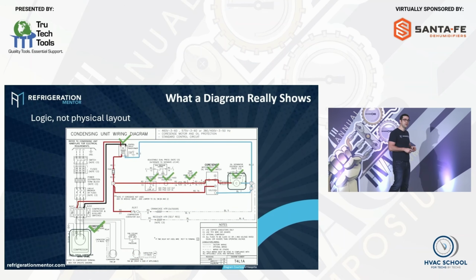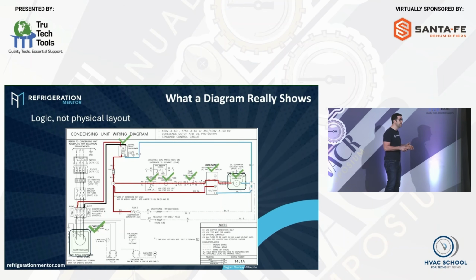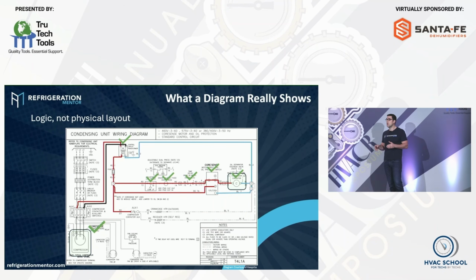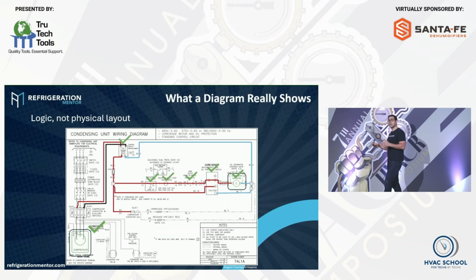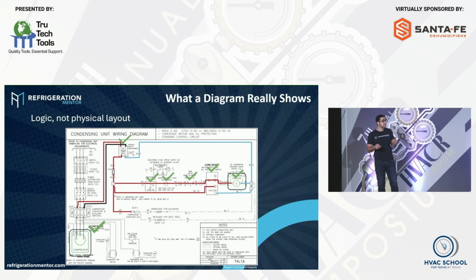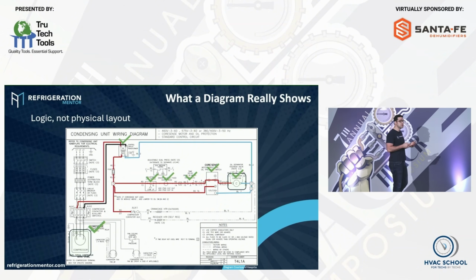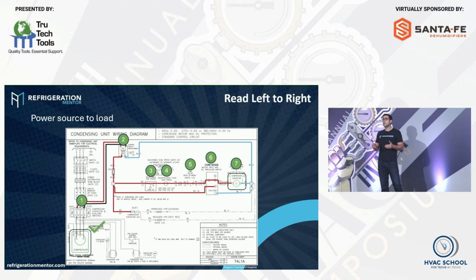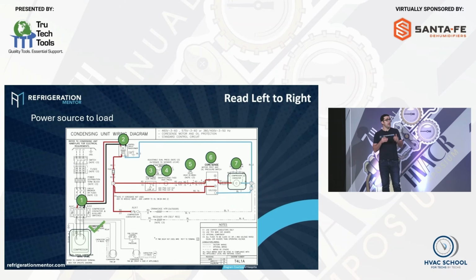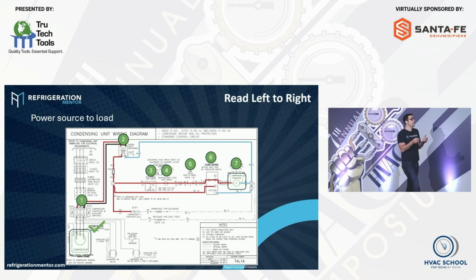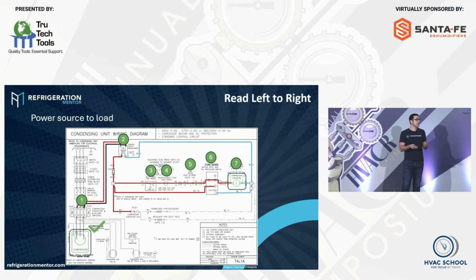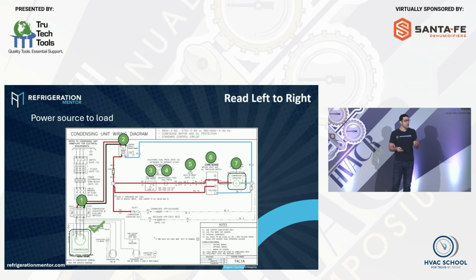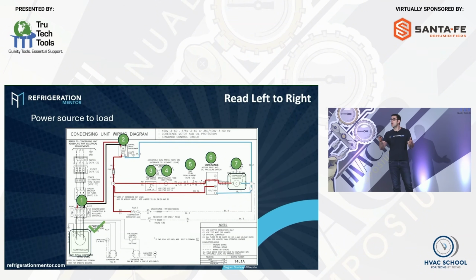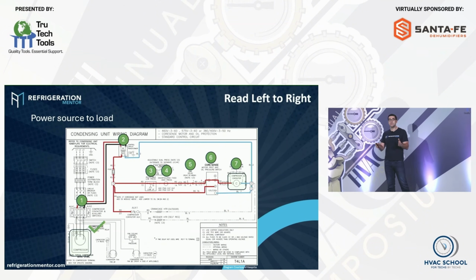What a diagram really shows is logic, and that's kind of what I want to teach you today, logic. It's not where those wires go. It doesn't matter where the wires go. It matters if you understand the logic behind it. This is so important. How does that voltage move? Okay? We want to read diagrams from left to right. From left to right. So as we can see here, we start and our main power comes down from our L1, L2, L3. When we're looking at a diagram, we're looking at a control circuit. We have L1 on the left, we have N or common or L2 on the right. So you got to remember how to read these diagrams.